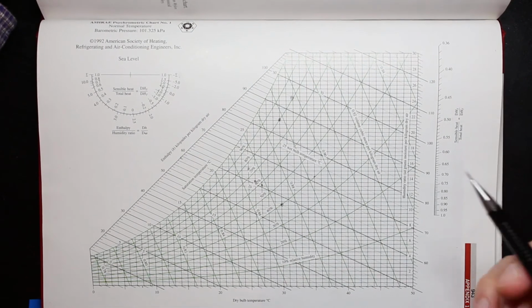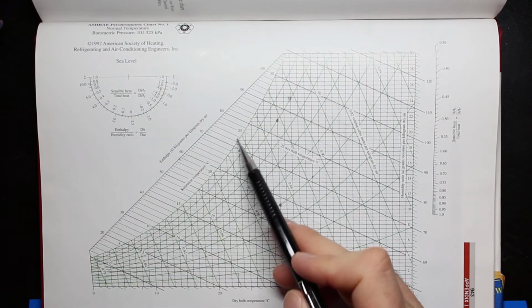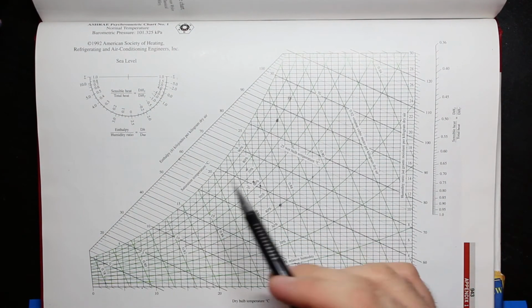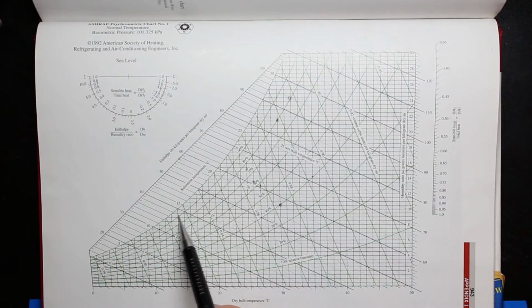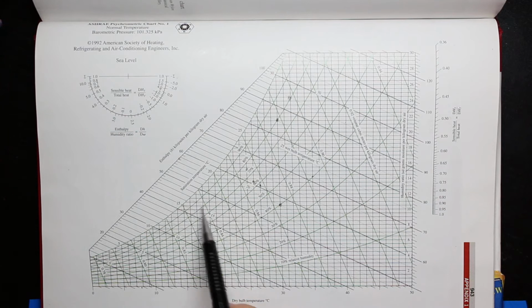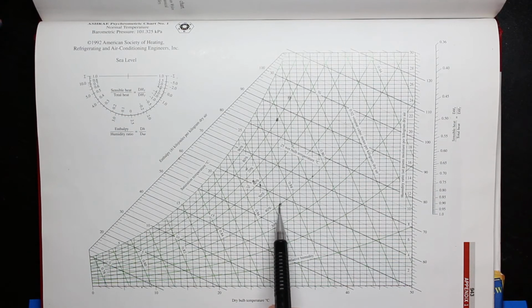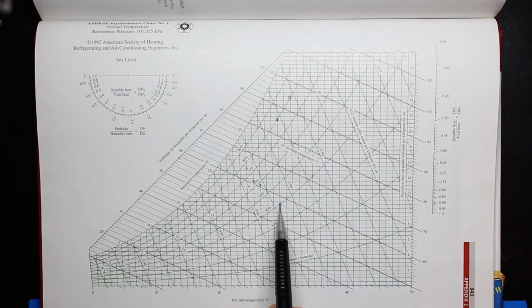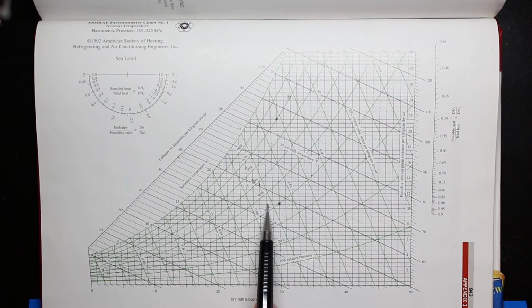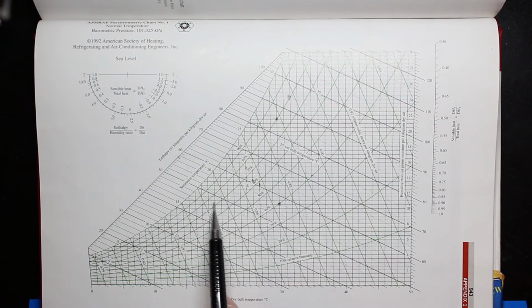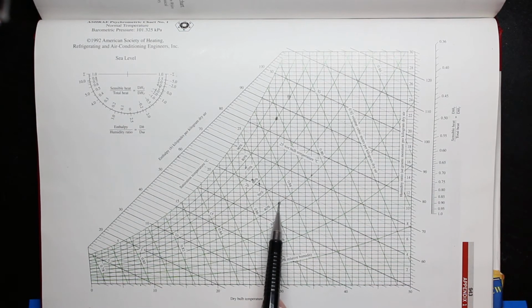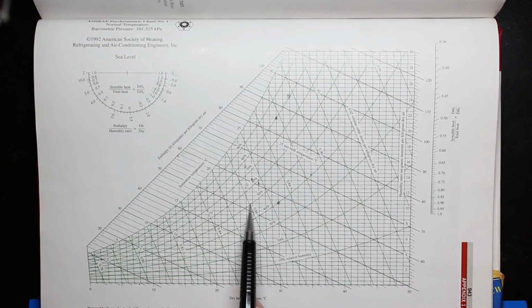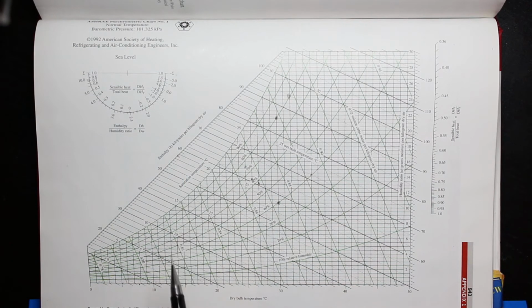Now, I want to talk about the temperature, the dew point temperature. So for dew point temperature, what you want to do is go horizontally to the left, all right? The reason behind that is for a given point, we want to decrease the temperature, which is this horizontal axis, until we have saturation or 100% relative humidity. So to obtain the dew point temperature from your point, you go horizontally to the left and read that particular temperature.